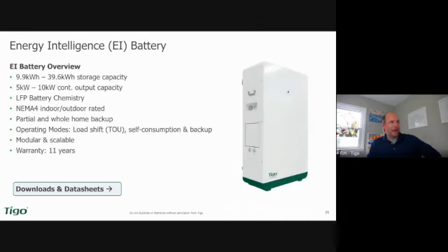Moving over to our battery system. So you can see this is the cabinet. Inside of each cabinet is a 3.3 kilowatt hour battery. You have 3 of them. That gives you 9.9 kilowatt hours of storage. What's nice about that is we ship the battery cells, which weigh about 50, 60 pounds, in the cabinet, which weighs about 50, 60 pounds, on a pallet, but they're separate. So in total, they're about 300 pounds total.